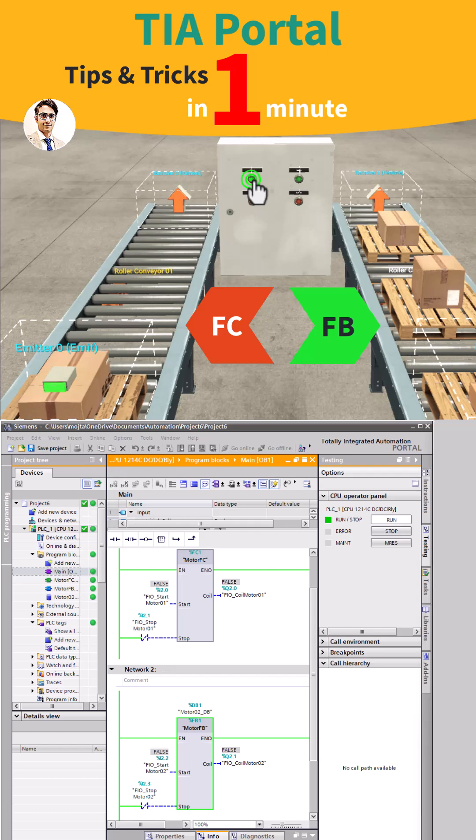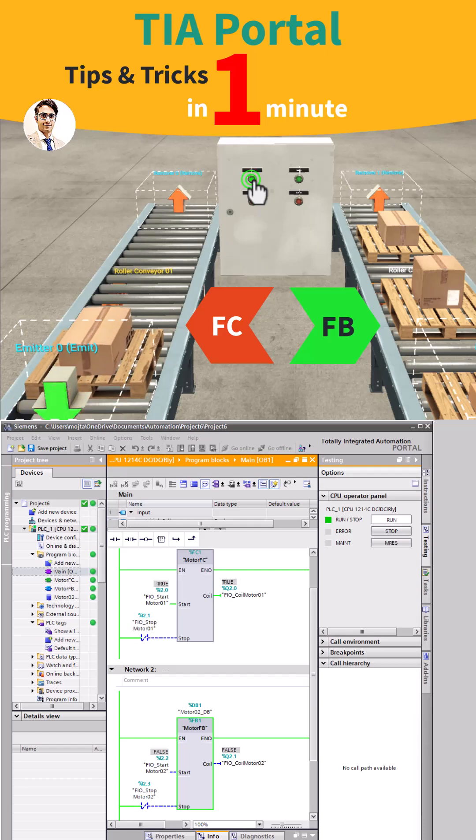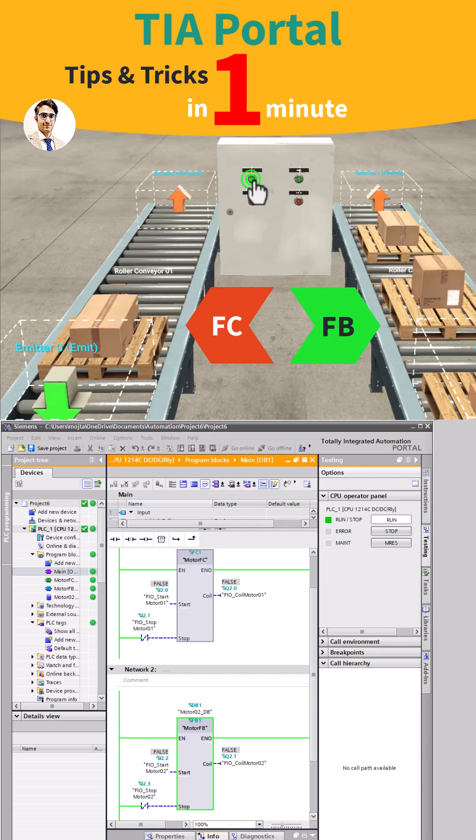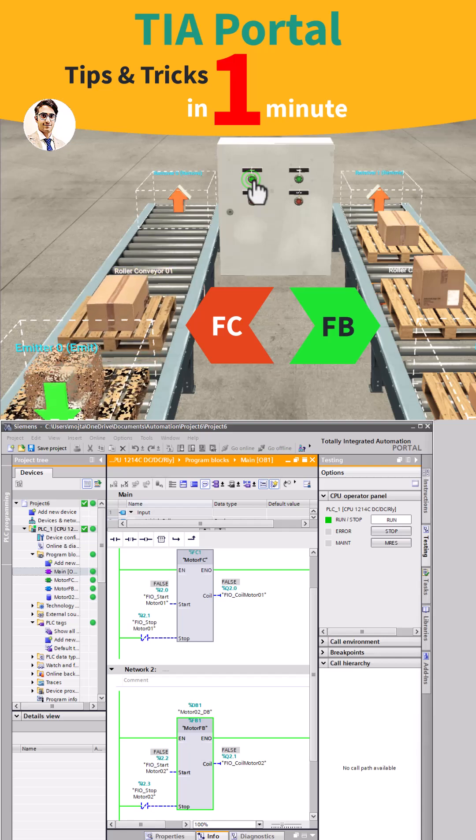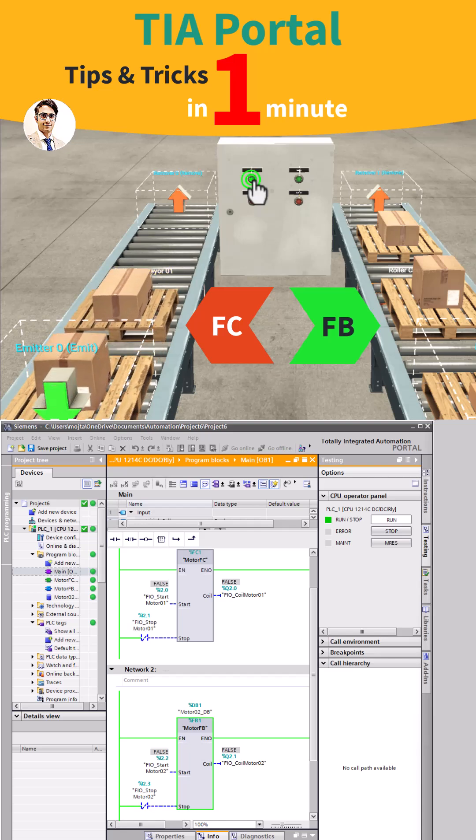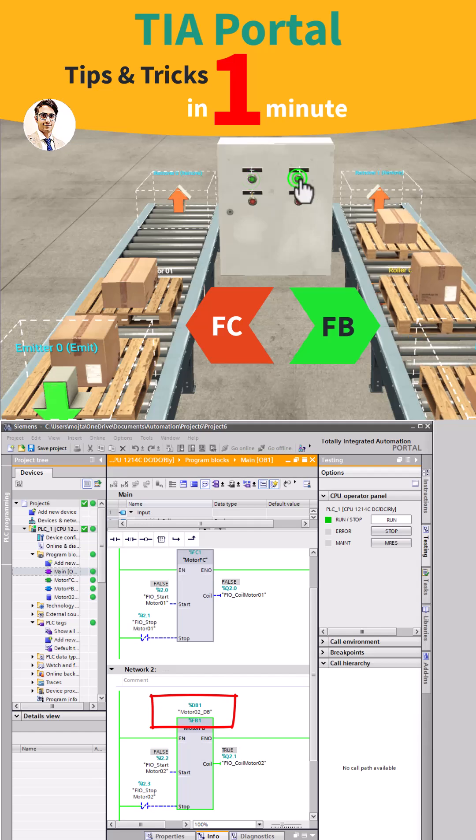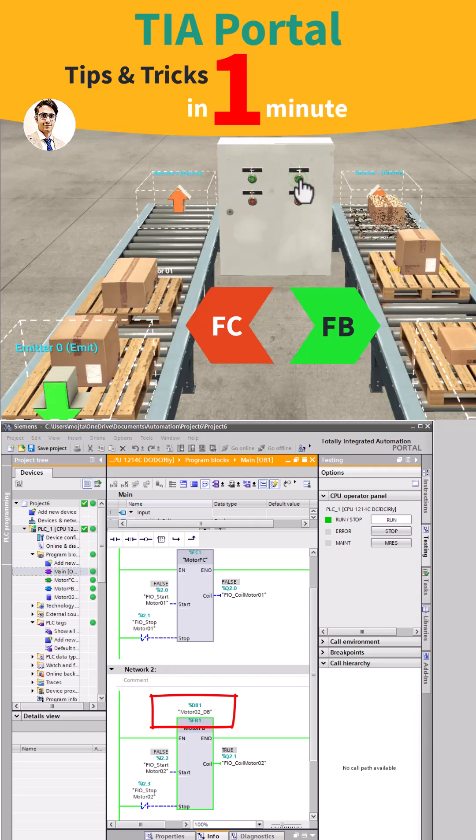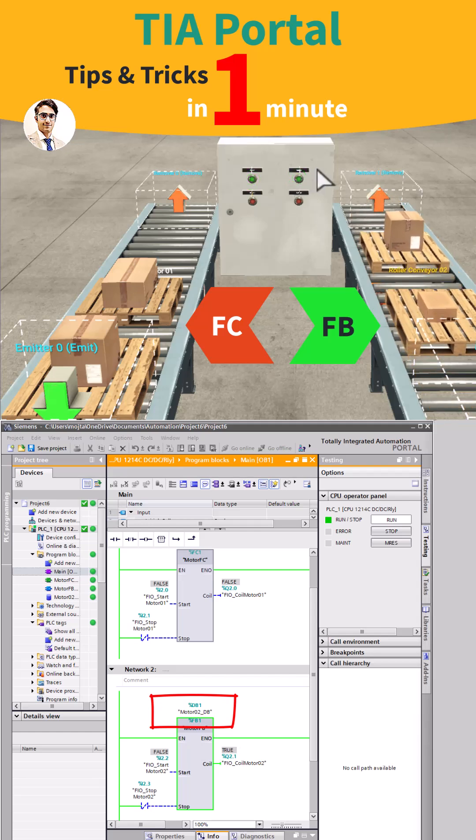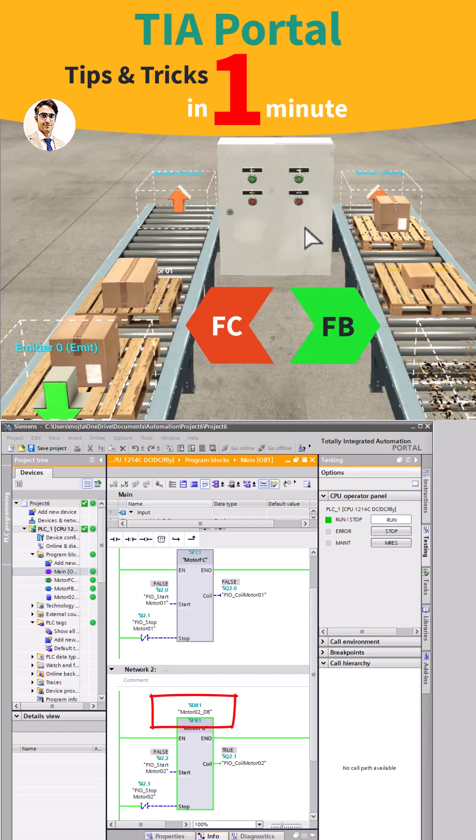But for the left conveyor that is based on function, as soon as you release the start button it stops. So the FC works without memory while the FB stores the motor's state, and it is because FB has its own data block.